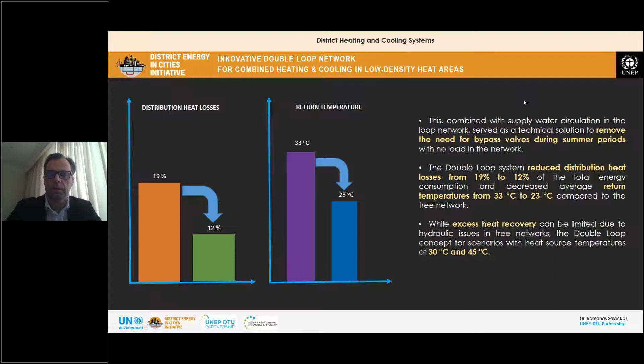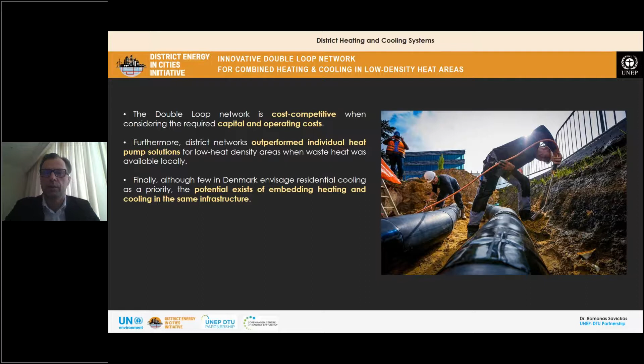This double loop network is cost competitive when considering the required capital and operating cost, and this network outperformed individual heat pump solutions. What we see as a very hot topic is comparing whether we should install individual heat pumps or switch to district heating networks, also for low density areas when waste heat was available locally. It shows very positive and good results for the final customer. Finally, in Denmark, residential cooling is becoming a priority in some cases, so the potential exists of embedding heating and cooling in the same structure, and we can utilize this double loop network.